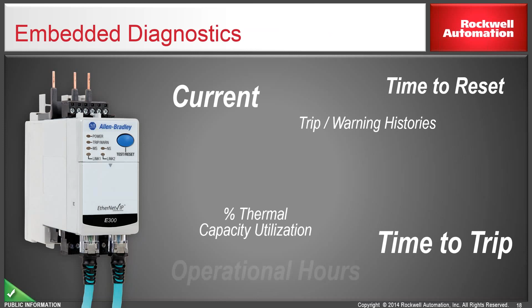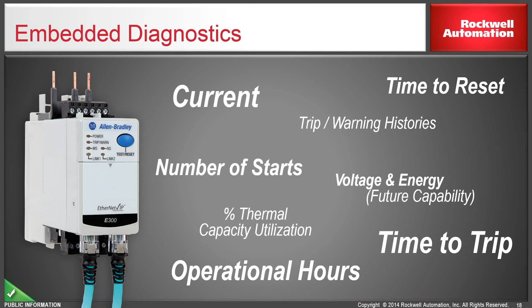So as you see on the left-hand side, this is the E300 relay, which is a combination of a sensing module, a base relay, and a control communication module. On the top is a communication module which has dual Ethernet IP ports. It will give you the current information. It will give you the number of starts. It will give you thermal capacity utilization. It will automatically profile the thermal capacity utilization of the motor, how much time the motor is running. It will give you voltage and energy, time to trip, and warning histories.